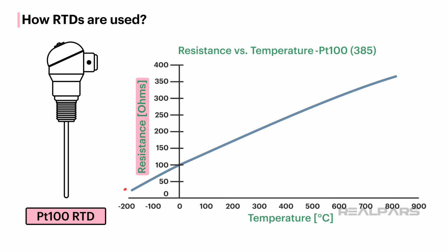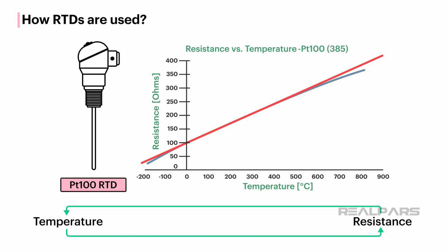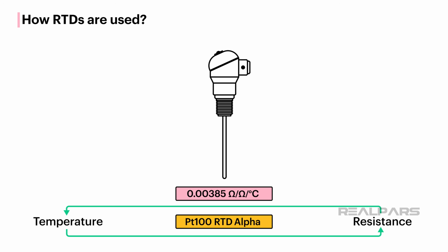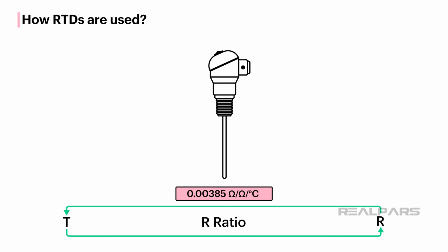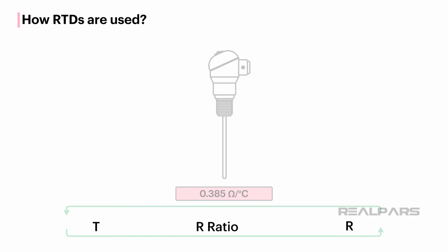The resistance changes almost linearly with a temperature change. A very good linear range for the PT100 RTD is 0 degrees Celsius to 400 degrees Celsius. The relationship between temperature and resistance of an RTD is referred to as the temperature coefficient, or alpha. The alpha of a PT100 RTD is 0.00385 ohms per ohm per degree Celsius. We can boil this down to obtain what's called the resistance ratio of 0.385 ohms per degree Celsius.